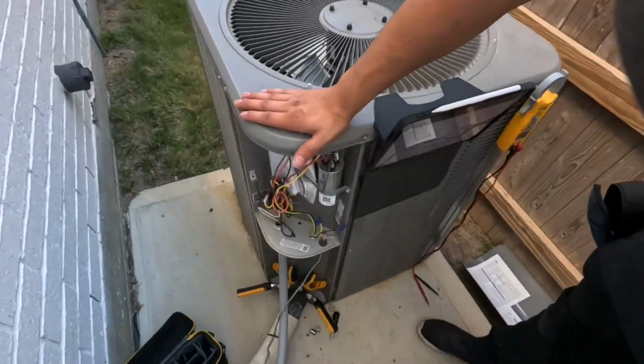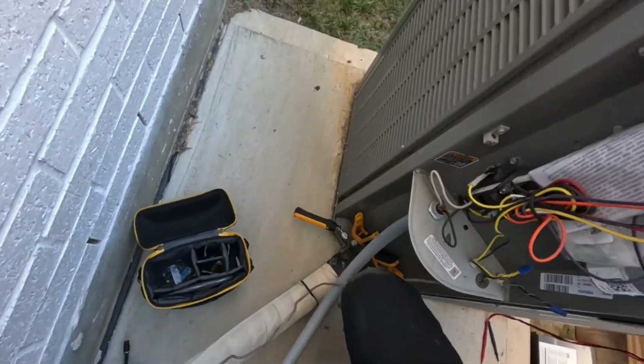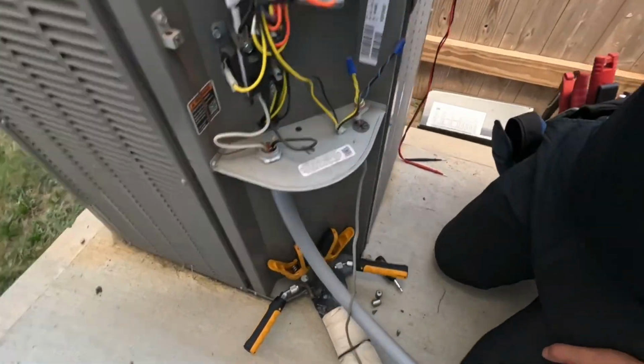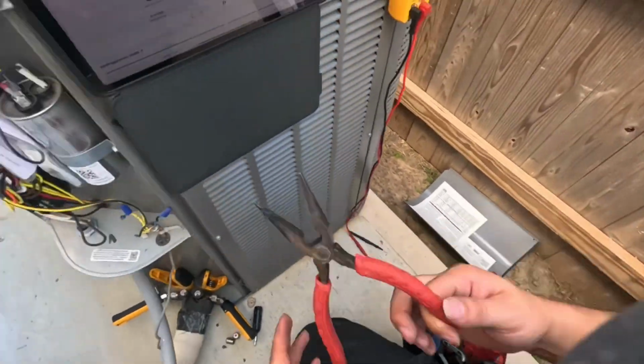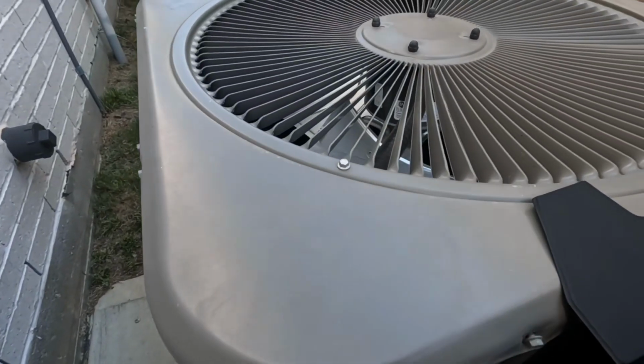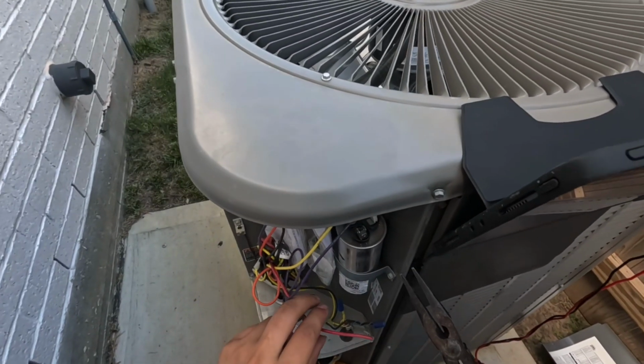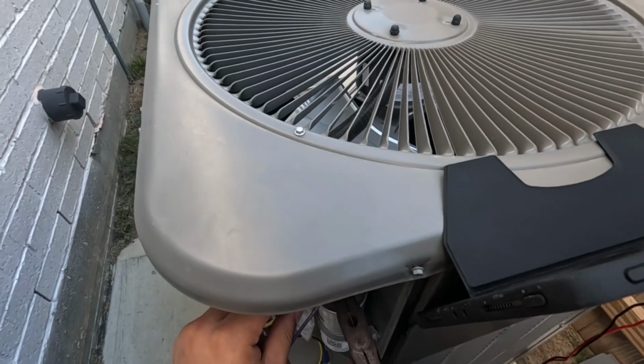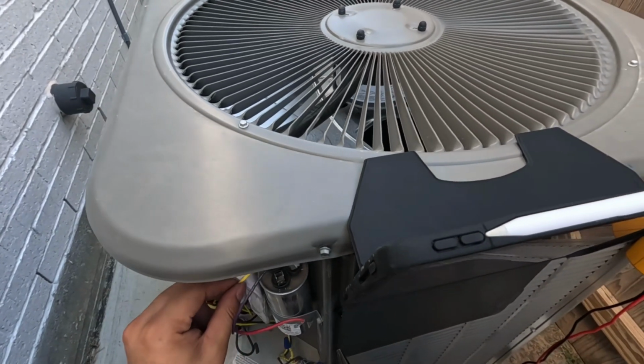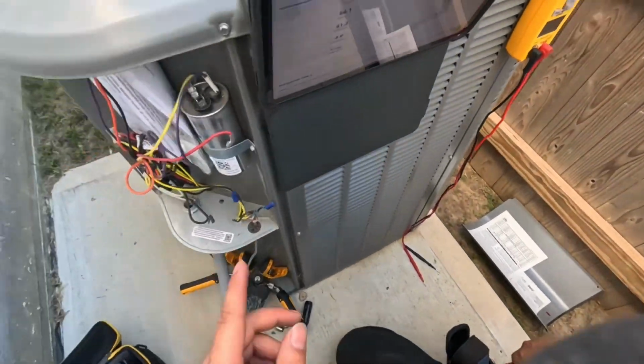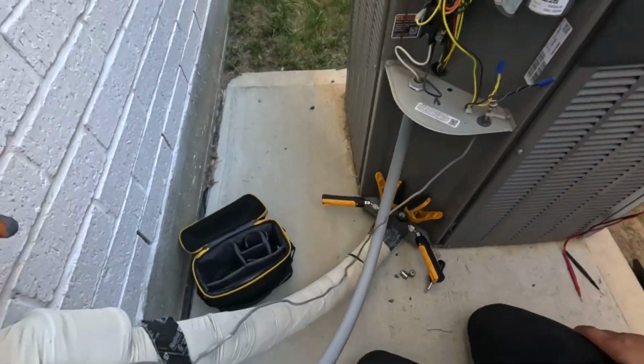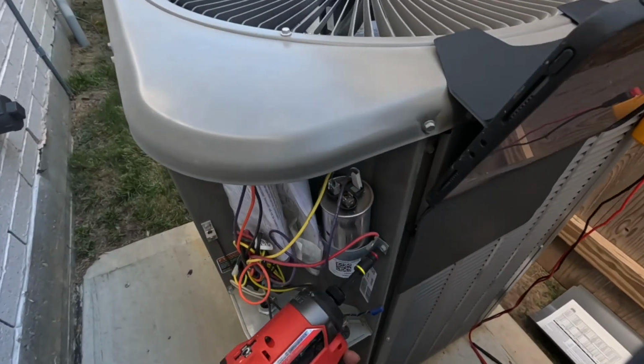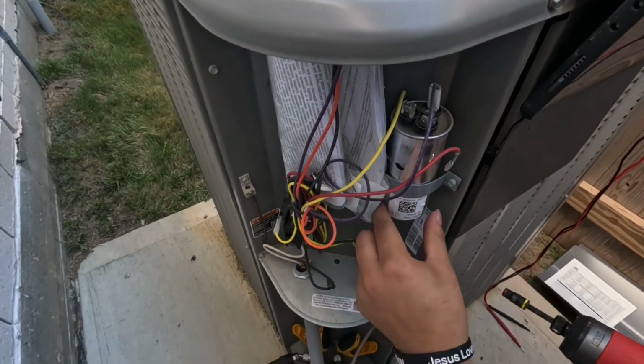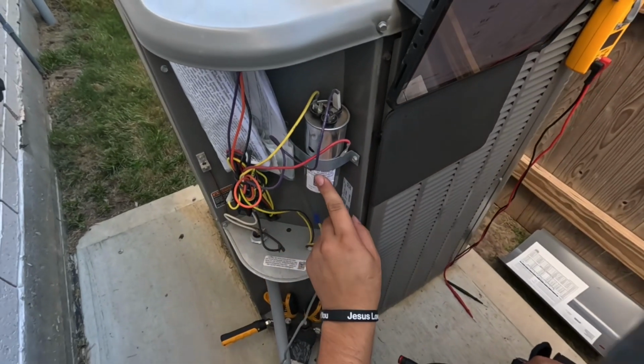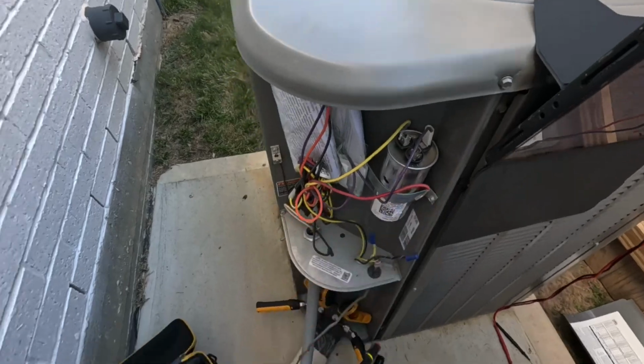I'm going to check the capacitor now. Yeah, I'm too old for this. Okay, so this is the common right here, this red wire. So that's power to the capacitor. And then this is Herm, this is for the compressor. Okay. No, there's no power on here. So also make sure you disconnect the power first. So we're gonna go ahead and loosen this screw. Bring it down. So it's supposed to be reading a 35 for the compressor and a 5 for the fan.